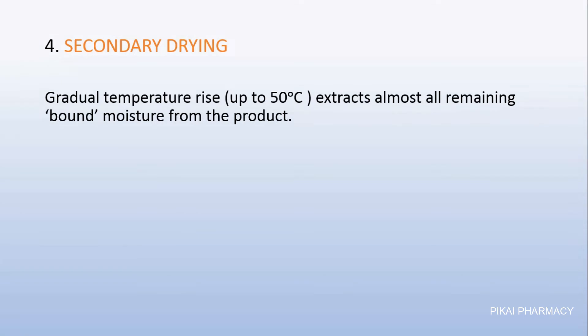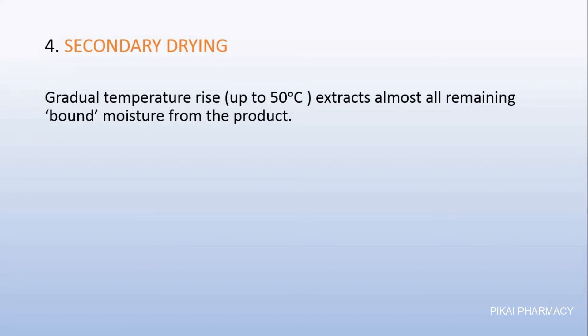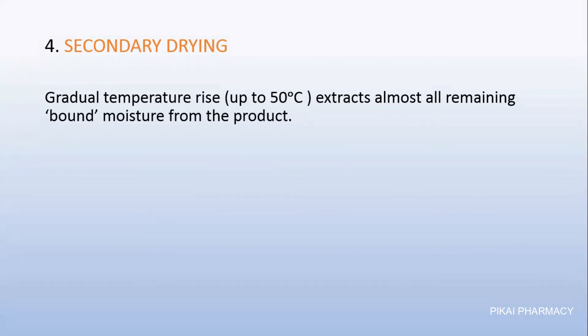The last step is secondary drying. Here we gradually increase the temperature up to 50 degrees Celsius — not more than that — as we are dealing with heat-sensitive products which might get degraded. We increase the temperature up to a certain value where the product does not get destroyed. We do this to extract almost all remaining bound moisture from the product. One hundred percent drying is not possible, but we try to achieve as much as possible. The threshold value is 50 degrees Celsius; increasing above that can damage the heat-sensitive product.